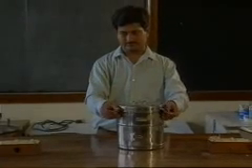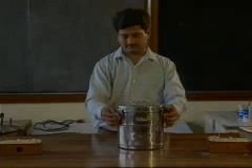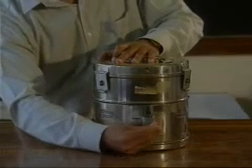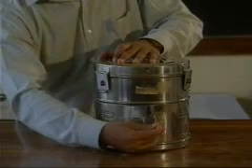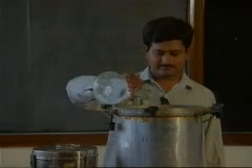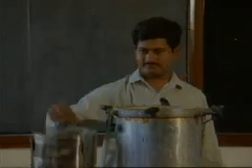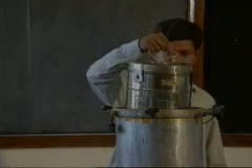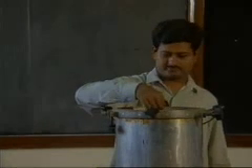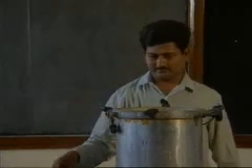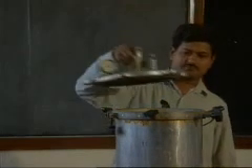After packing, the load is kept in the autoclave drum. The position of the holes in the drum is changed to open position. Sufficient water is poured in the autoclave chamber. The drum containing the load is kept on the perforated tray just above the level of water. The lid is then screwed down to close the chamber.